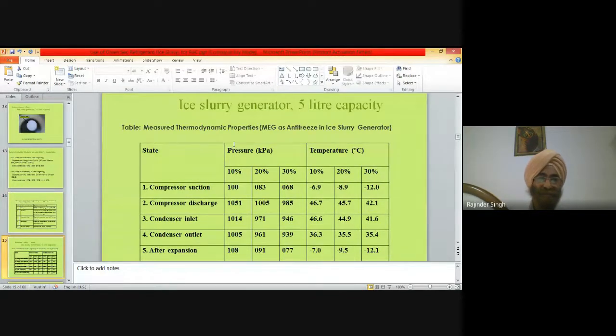Now this is important. These are the various measured thermodynamic properties using MEG as an antifreeze. In this, I took the various parameters like compressor suction, compressor discharge, condenser inlet, condenser outlet, and after expansion, pressures as well as temperatures. By using these, I did the calculations and I calculated the first law of thermodynamics. I calculated the COP of the system, coefficient of performance. I think all of you are aware what is the coefficient of performance of the vapor compression cycle. It is the ratio of net cooling effect divided by work required in the compressor.